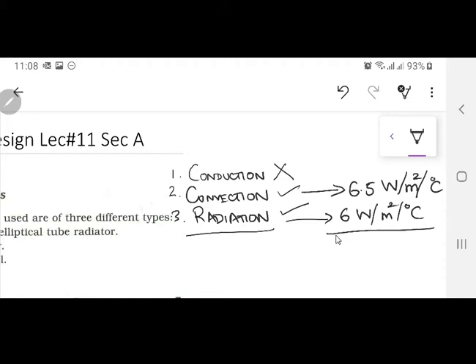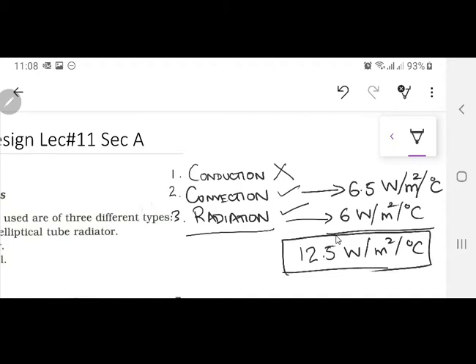Convection is a little more, you can have it over there. This means that from your transformer tank, if you add these two together, you have 12.5 watts per meter square per degree centigrade. This power can be dissipated from the transformer tank itself.